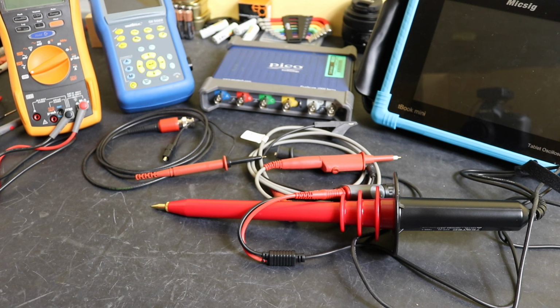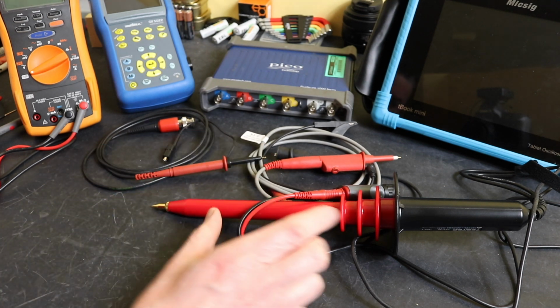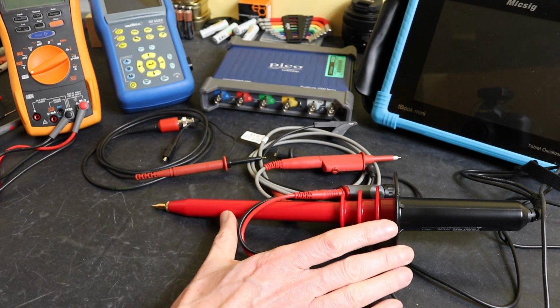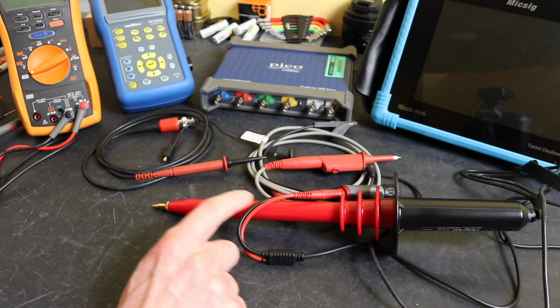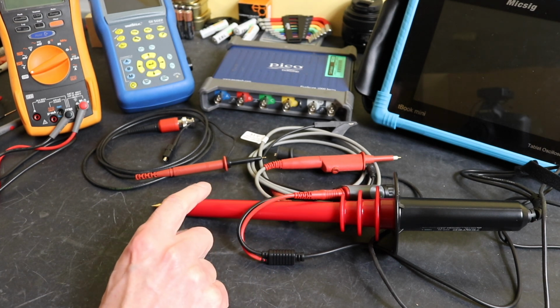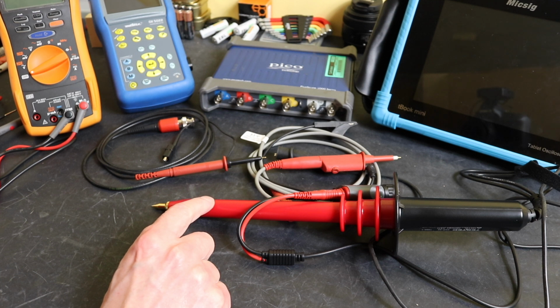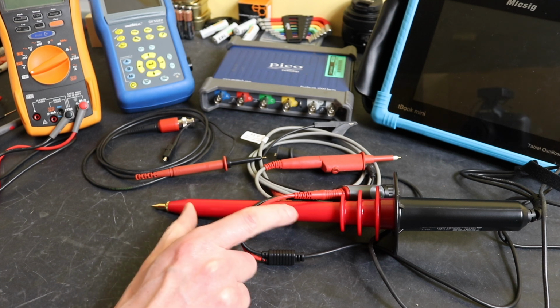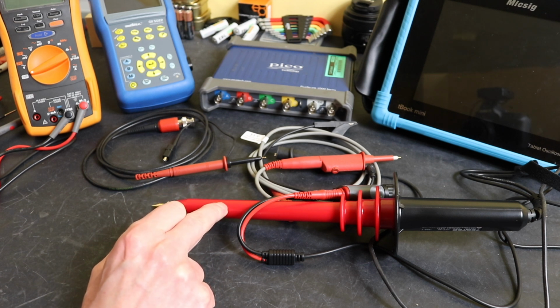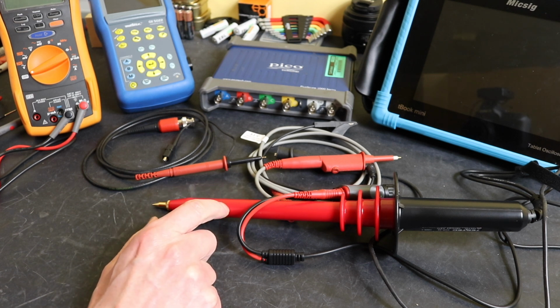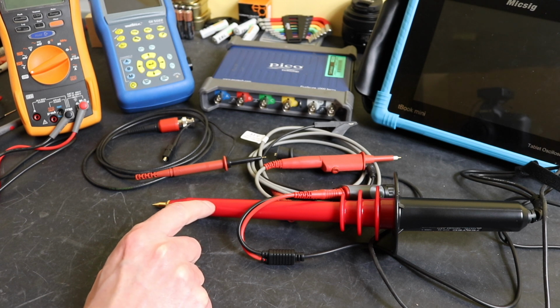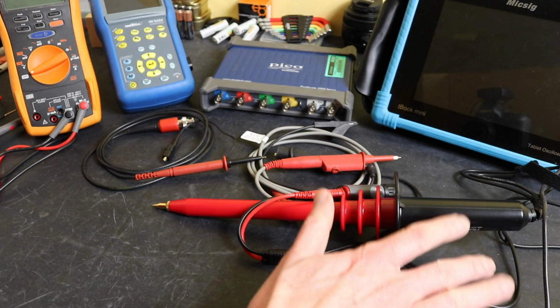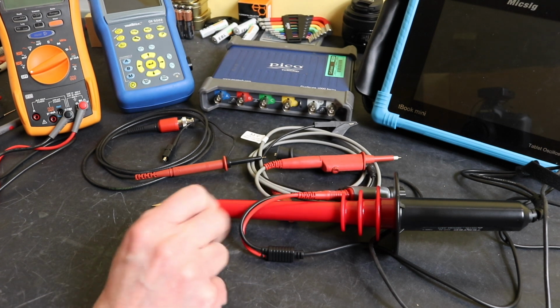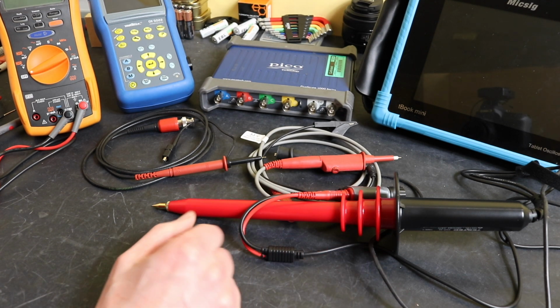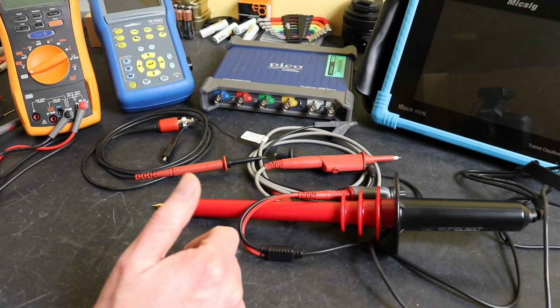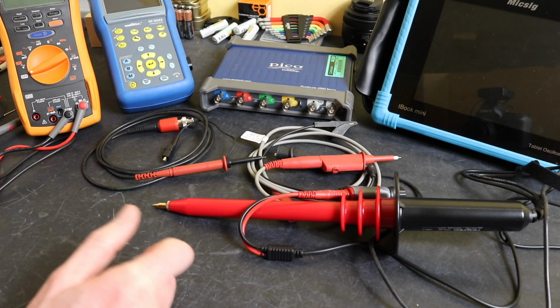One of the other differences that you'll see between these probes and these small oscilloscope probes is their physical construction. Obviously, this is much bigger, but the tube inside this is usually a chain of resistors. You do that because it can get you better stability with the ratio, having a number of resistors in there. Also provides an added safety factor because it's unlikely that all the resistors will go short circuit. An individual resistor going short circuit, you won't put as much voltage down and damage the equipment that this is connected to. And when you test the probe, the ratio will be out, so you'll know that something's happened inside here and it's gone wrong.